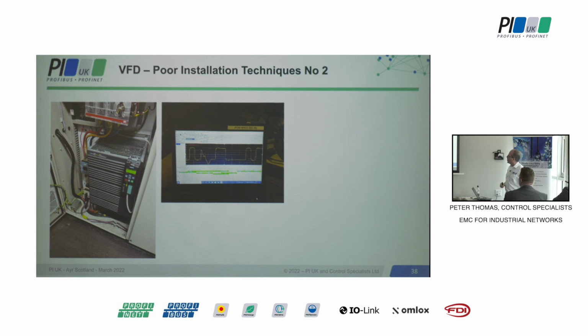This is what I saw on the Profitrace. Now, for those of you that know about Profibus, Profibus uses what's called RS485. It's a two-conductor transmission system. This isn't the signal on the red or the green, it's the difference between the two. So clearly there you think, ooh, okay, that doesn't look right. We're normally looking for nice square waves. But this tool has a useful feature where it allows you to look at the signals on both, the A and the B.